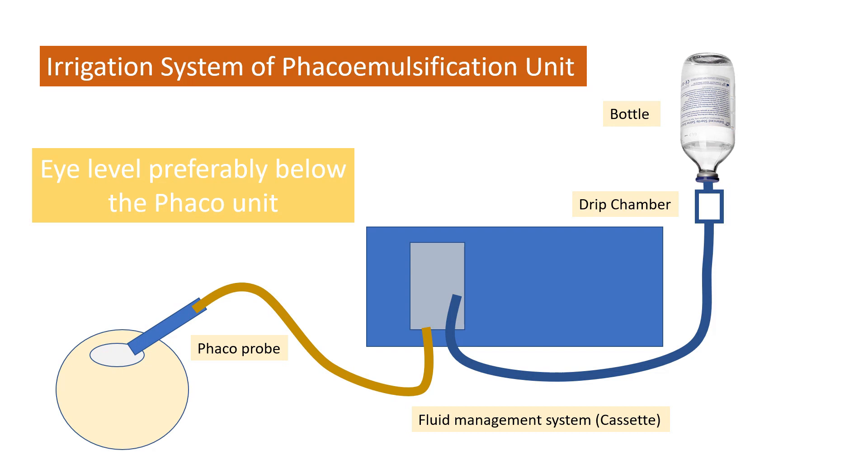When you set up the Phaco unit, it is preferable that the eye level should be below the Phaco unit, so as to maintain proper flow and avoid air entering during the irrigation.